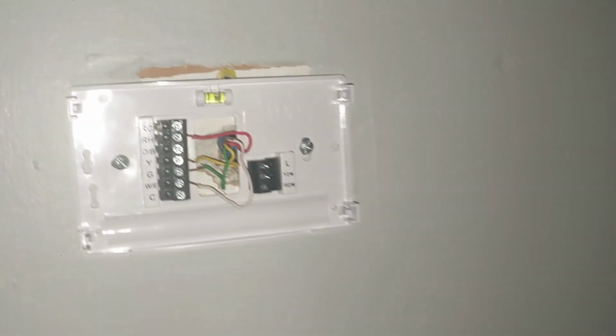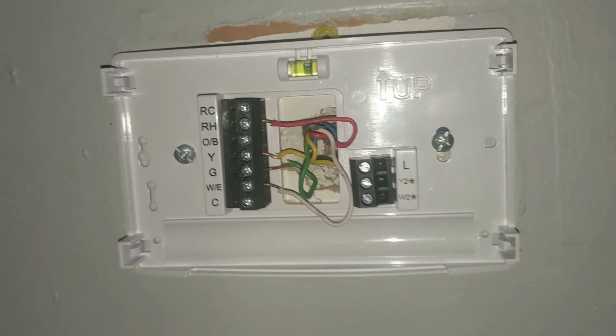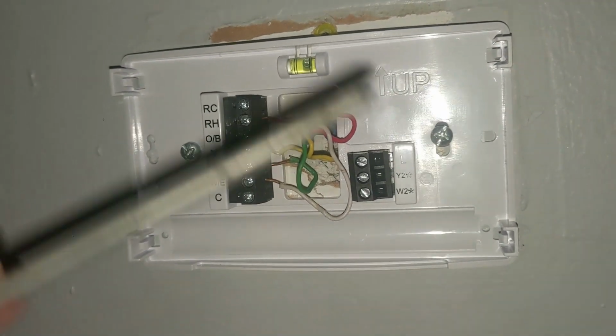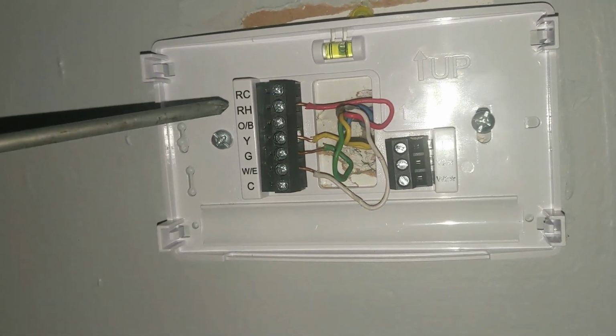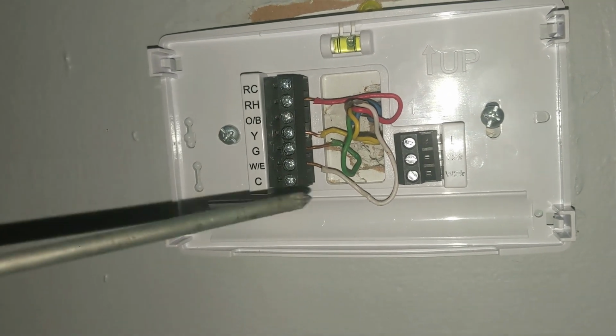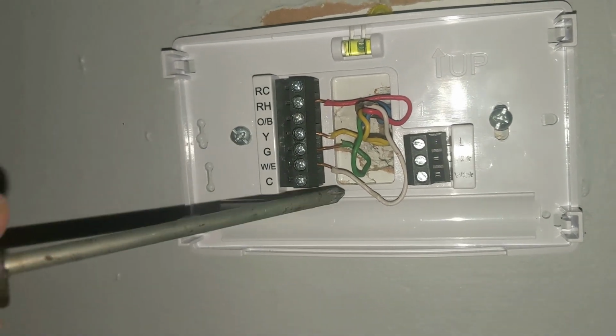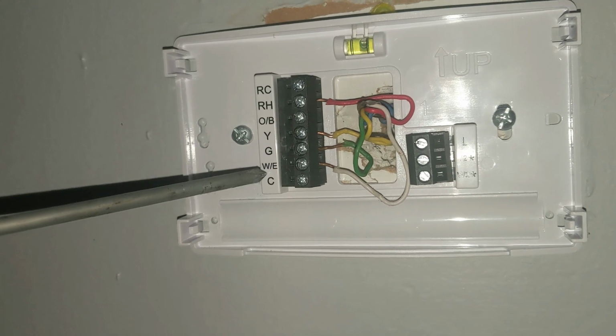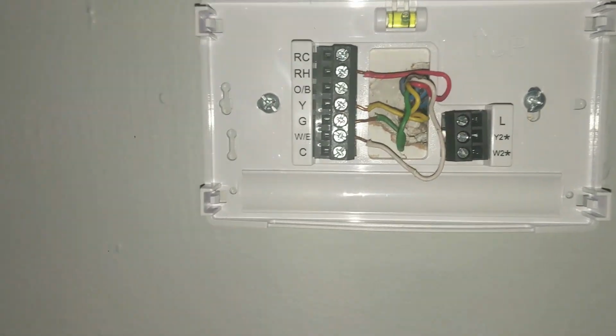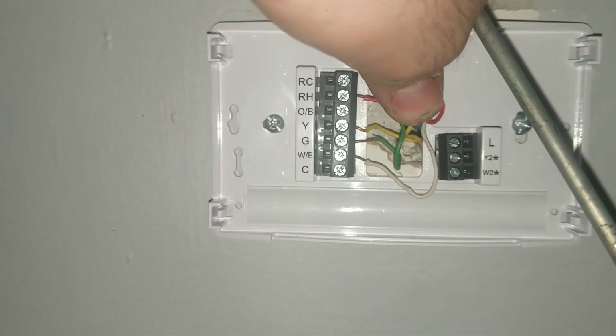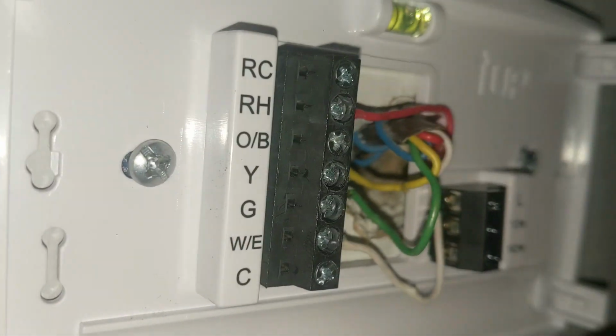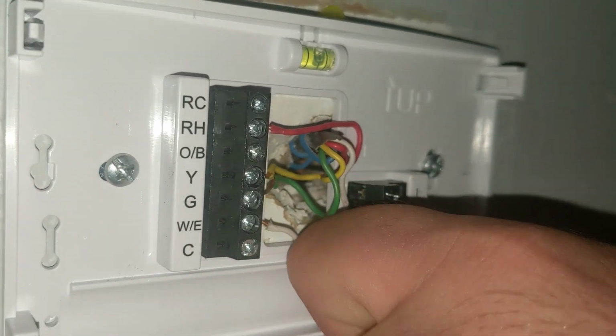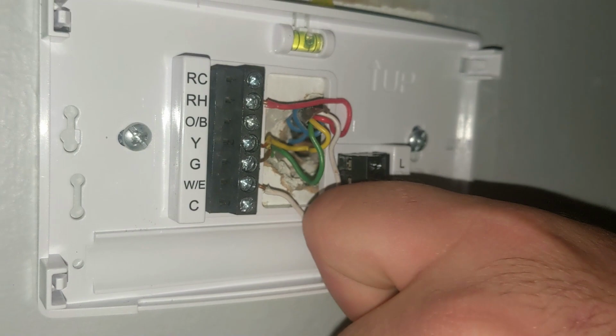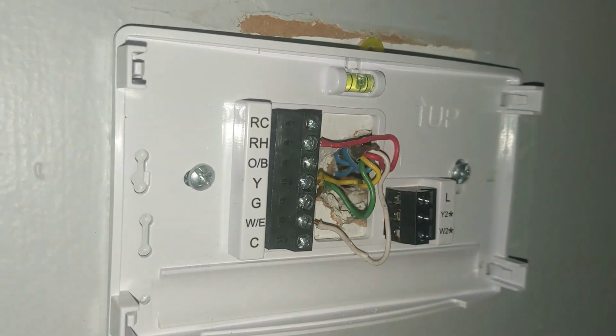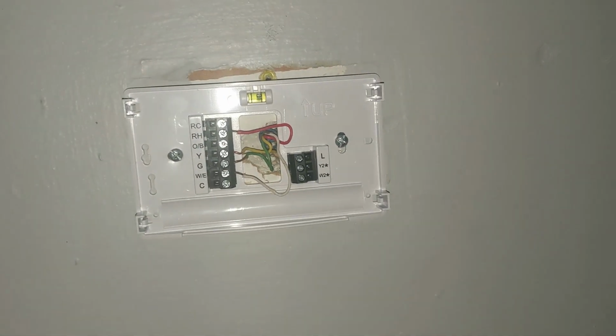Alright guys, I had to turn off the electricity, right? But now you guys can see this is what we did to wire this one. Red to RH, yellow to Y, green to G, and white to white or W. And we had to push this wire back a little bit. Make sure you don't push it in too far because it's gonna get stuck in the wall, okay? So now we are set up and ready to go.